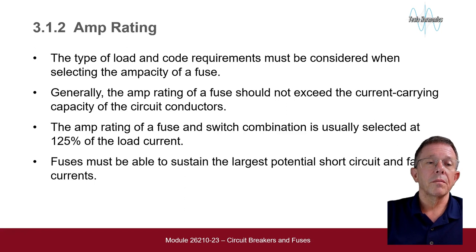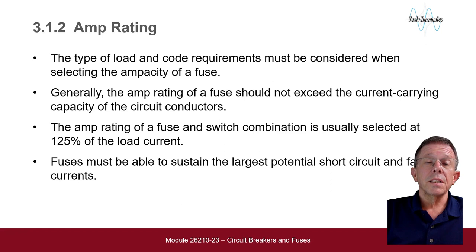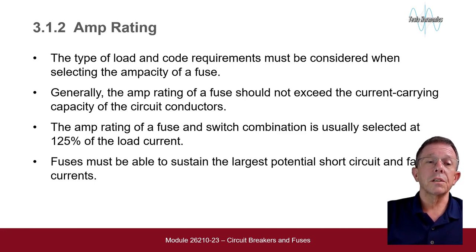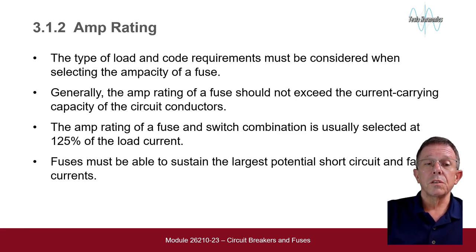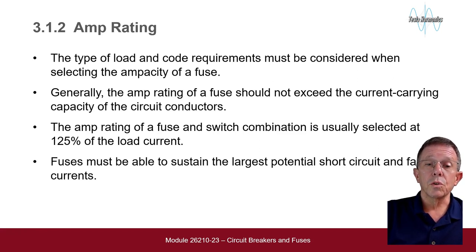Ampere Rating. The type of load and code requirements must be considered when selecting the ampacity of a fuse. Generally, the amp rating of a fuse should not exceed the current carrying capacity of circuit conductors. The amp rating of a fuse and switch combination is usually selected at 125% of the load current. Fuses must be able to sustain the largest potential short circuit and fault currents.